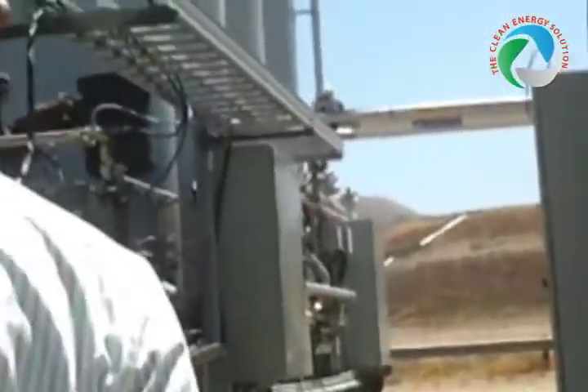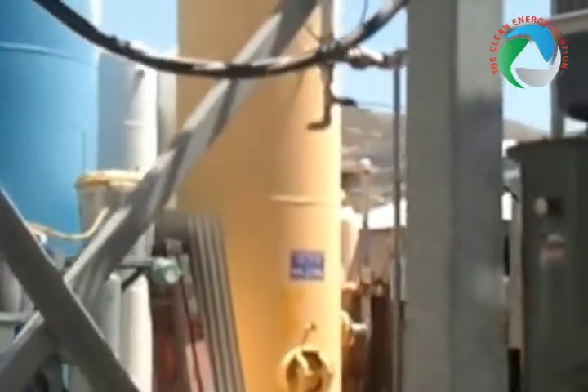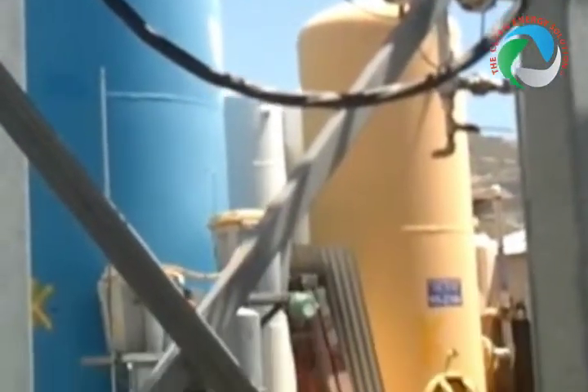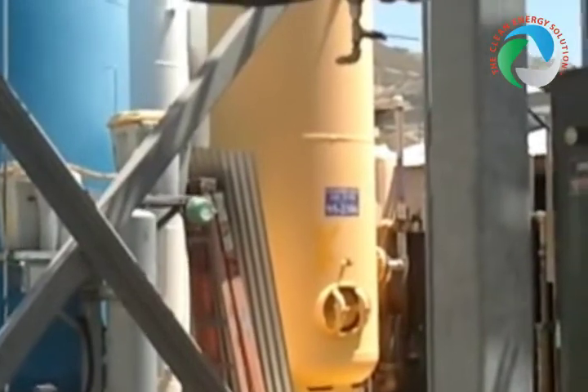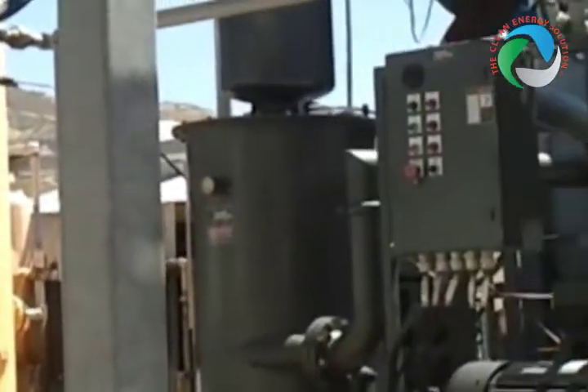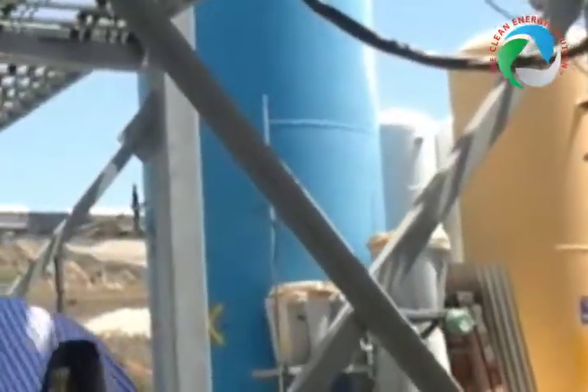Now, there is a nitrogen generator that basically is for the process of the TSA. Nitrogen is used in purging the cold box. Nitrogen is used in the refrigeration loop, so it's make-up to that loop. And it's also for purging for TSA purposes.